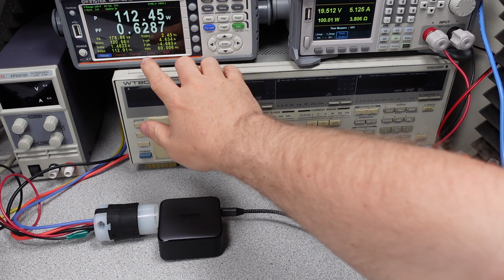So here we are, running 100 watts on the wall power adapter, and we can see it does not have power factor correction, so we're running pretty low. Let's look at the graph for this one - it's very spiky and peaky, so it's not very pretty. It's certainly not what we want to see, with very large peaks for the current values at this 100 watt setting.